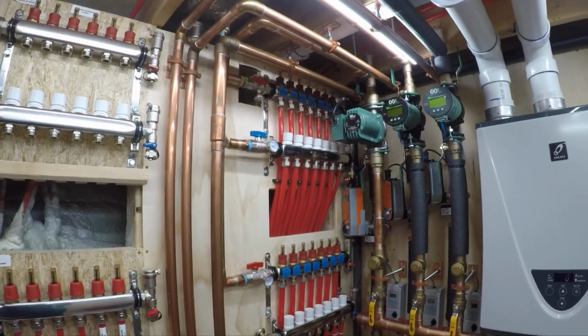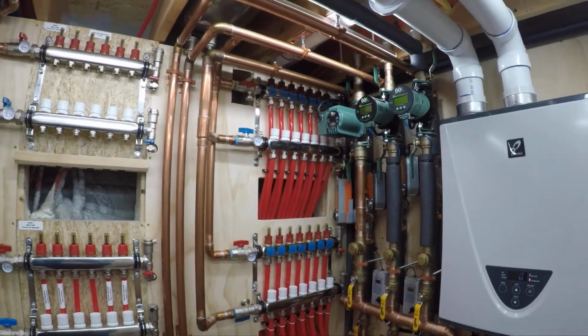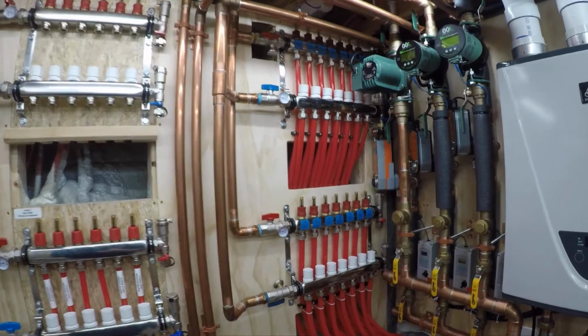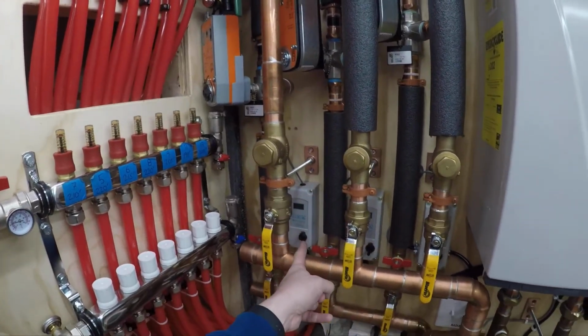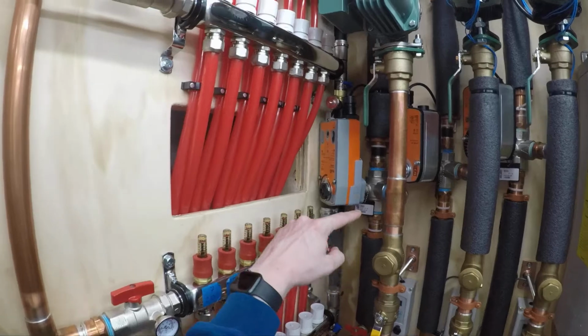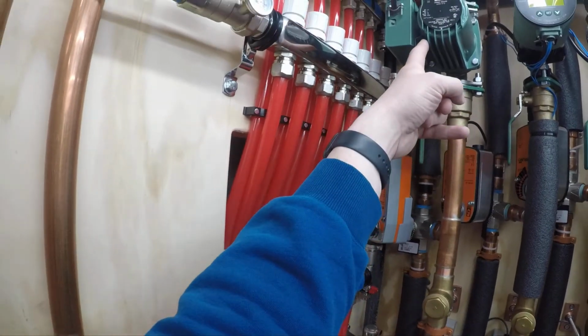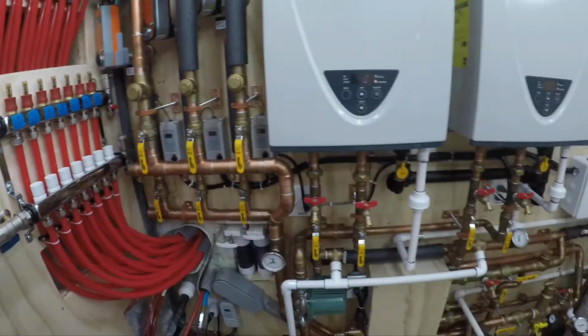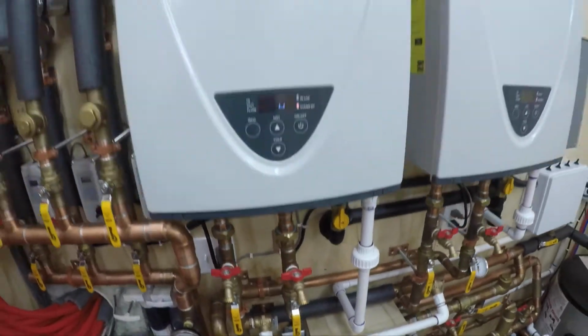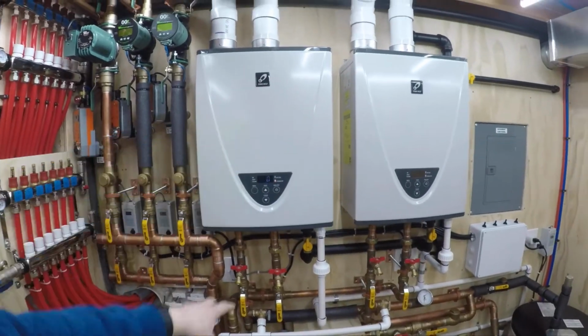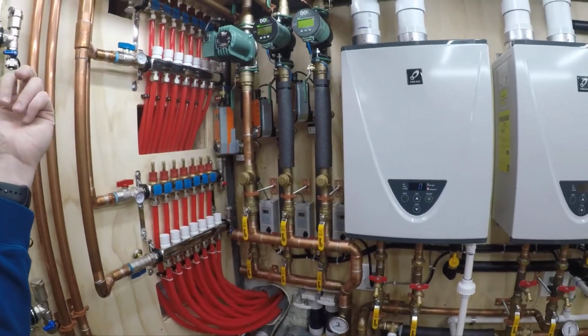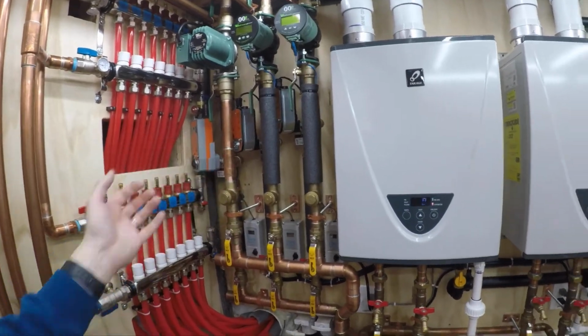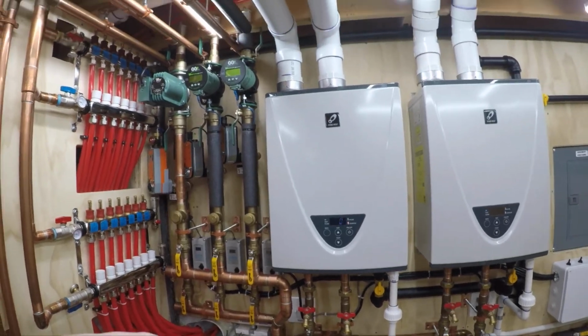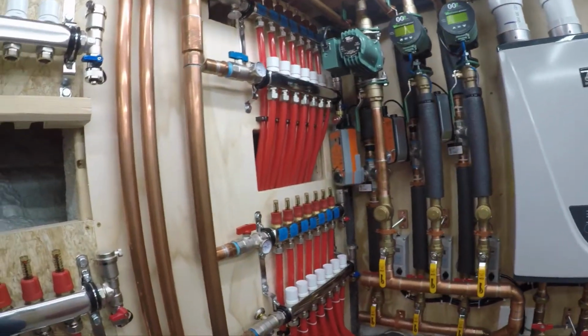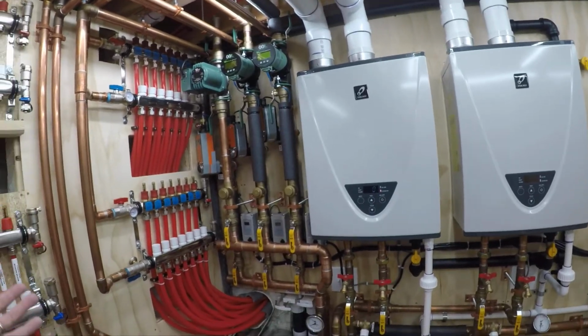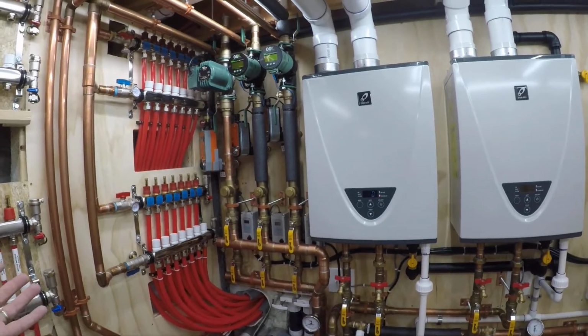It gets all the way down to 65 and says, I need more heat. Once it hits 65, the aquastat energizes. It opens the three-way valve to now allow glycol to go down through the return. It energizes this pump, turns on the heaters, and starts to pick up more heat for the driveway. Once it heats it back up to 80, it turns it off. So it's very efficient in that it's not running non-stop. Even when you're melting the driveway, the system is really, it'll even out.